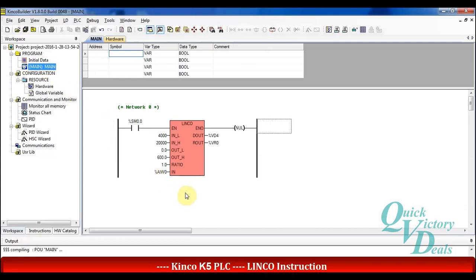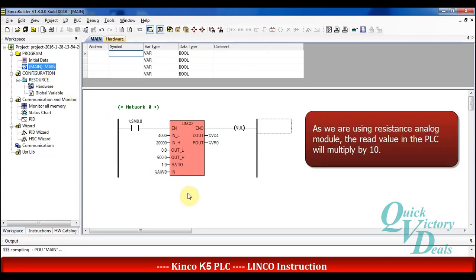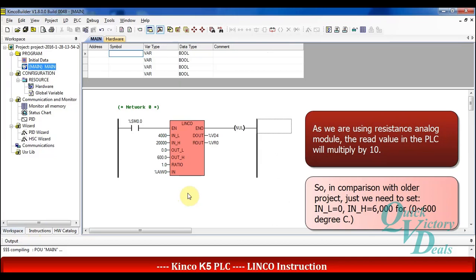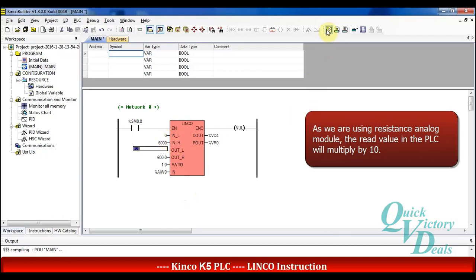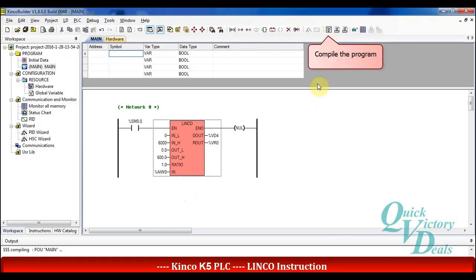As mentioned before, when reading an RTD sensor with an RTD module, the value in the CPU is multiplied by 10. So in this new example we just need to change INL and INH. We should set 0 and 6000 respectively. After compiling the program we don't have any errors.